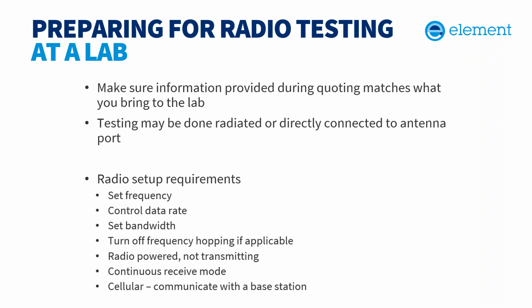Another thing is for radios, antenna port testing may be required depending on the radio and what testing is needed. This may involve soldering a pigtail and an SMA connector onto the circuit board if it has an integrated antenna. So if there's a chip antenna, some testing might still need to be done direct connect, so you'll need to solder onto that board to get that connection. Also, some clients ask us what they need to do to configure the device properly for testing. Basically, how do you control the radio? It depends on the scope. System approvals and original approvals for modules are more complex, so they require more control compared to integrating an approved module.